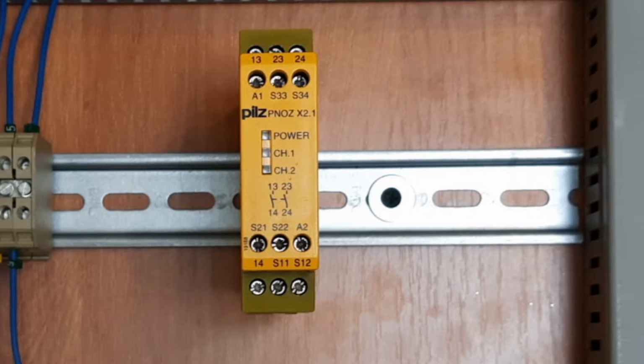What we've got here is a Pilz safety relay X2.1. I'm going to use it in application with e-stop button. This safety relay has got two safety inputs, S11, S12 and S21, S22. Two safety outputs. Start circuit S33, S34, which is used either for manual or automatic start. And three LEDs for status indication.